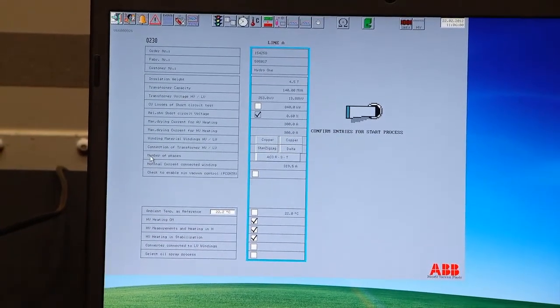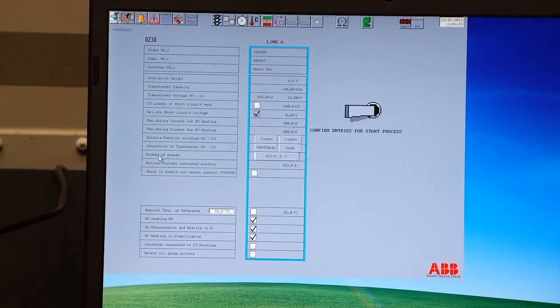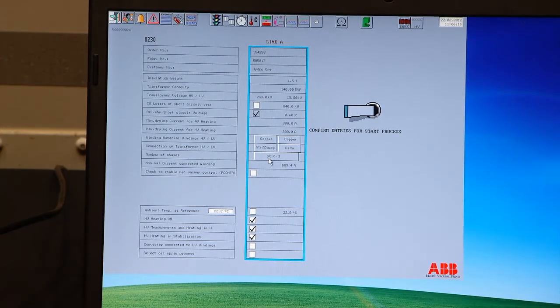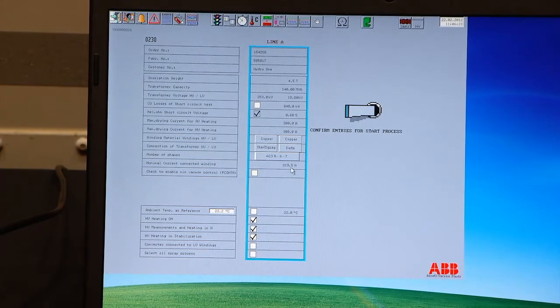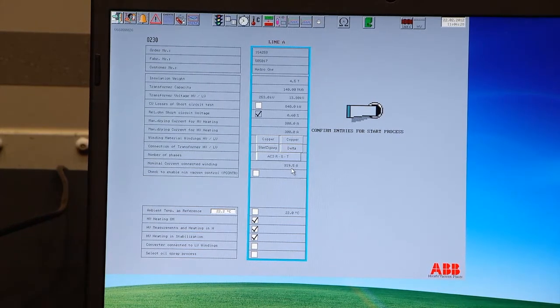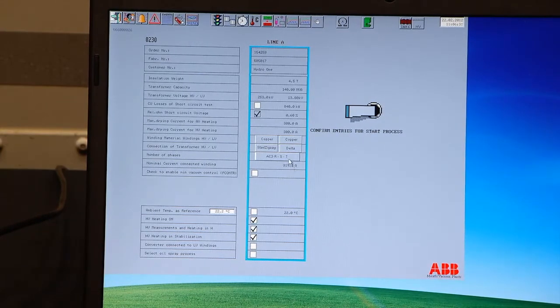The last input from the transformer data sheet is the number of phases. If it's a single phase or a 3-phase transformer, you click, it changes to single phase, you click again, you can go for direct current heating, very seldom used, and in this case we have 3-phase. The nominal current for the transformer is calculated. Check that again against the data sheet, that this is correctly calculated. That's basically all the information from the transformer data sheet.